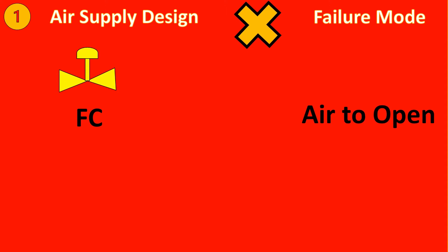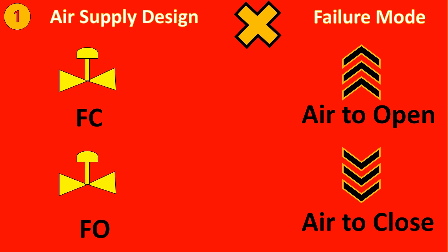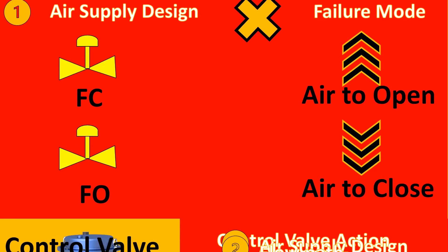Now let us look at interesting part which is that air supply design we can see as a thumb rule is basically opposite to the failure mode. So for a fail close valve your air supply has to be air to open. So in case of air failure it will go to close because of the spring. Similarly for fail open the air supply always has to be air to close. Remember this.